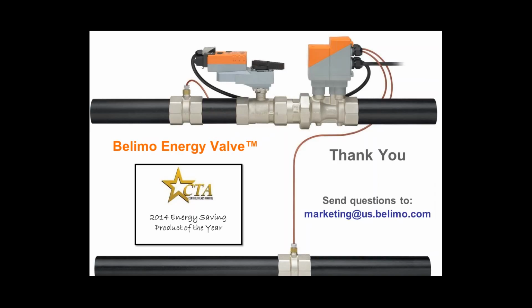When you do that, you're always weighing occupant comfort or space condition versus energy savings. That's what's neat about Energy Valve: you can choose higher or lower demands for delta T based on how critical that space requirement is. And as we responded to the previous question, or maybe it was two questions back, we can always write a routine that says, when we're not effectively cooling this space, immediately disable the delta T management.